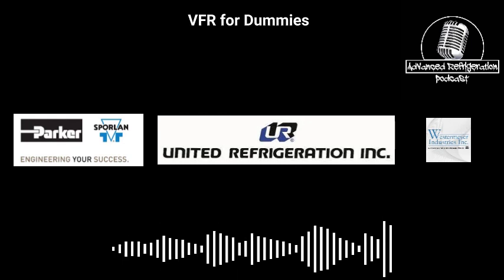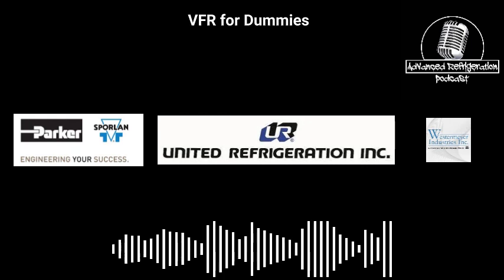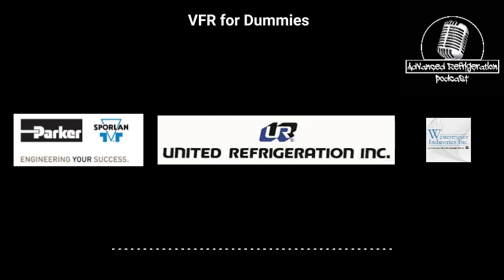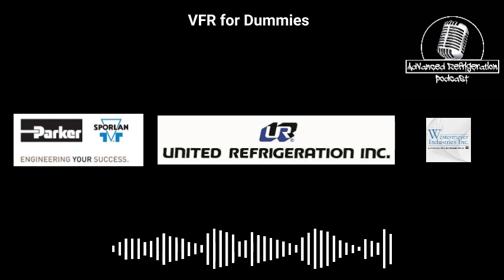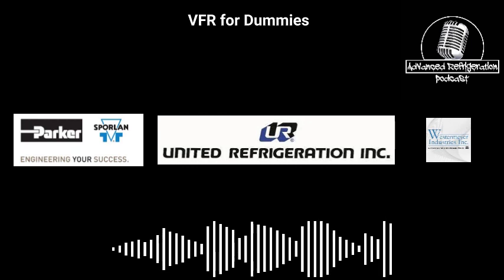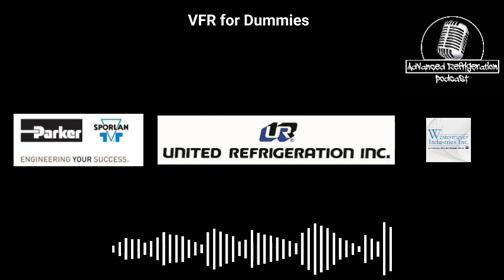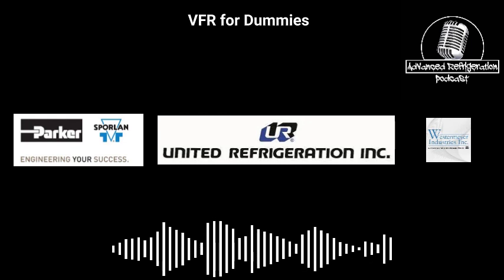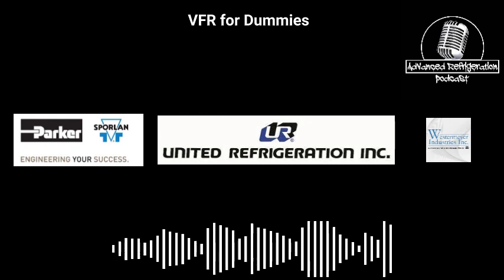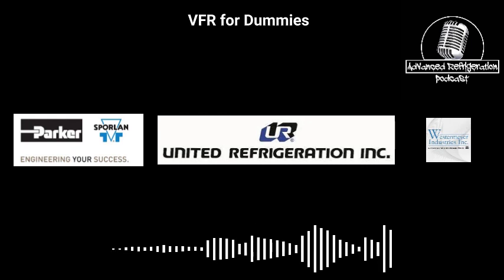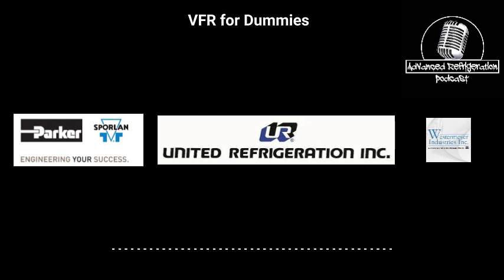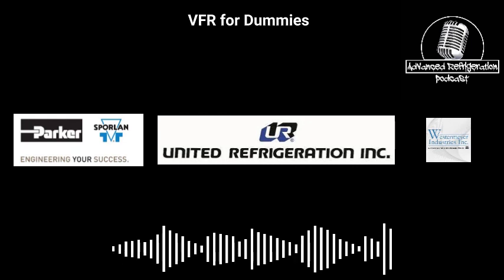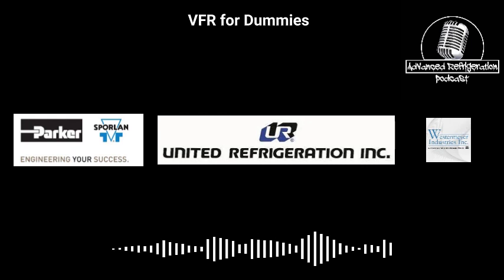Now, with the Daikin stuff, is it mostly the Ys and stuff I've seen, or is it all branch box stuff? I'd say the most common thing that I see day in and day out is cross control wiring. What happens there is you'll have one head calling for heating, another head calling for cooling. The wires are switched. The branch selector doesn't know any different. It's sending the refrigerant, so the coil that's calling for heat is now getting cold refrigerant, or it's getting the liquid instead of the hot gas. And that just causes a flooded condition. That's probably the most common thing that I see that leads to compressor failure.